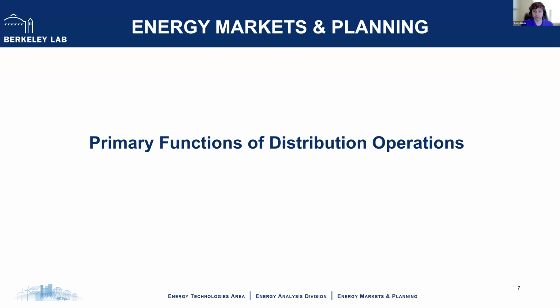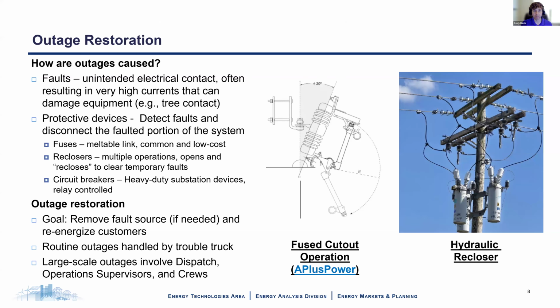Okay, so talking about the primary functions of operations. What does operations actually do? Thing number one, outage restoration. So what is an outage and how does it actually get caused? Outages are caused by faults. These are unintended electrical contacts, generally resulting in really high current that can damage equipment. So a tree falling across multiple energized lines is sort of a classic example.